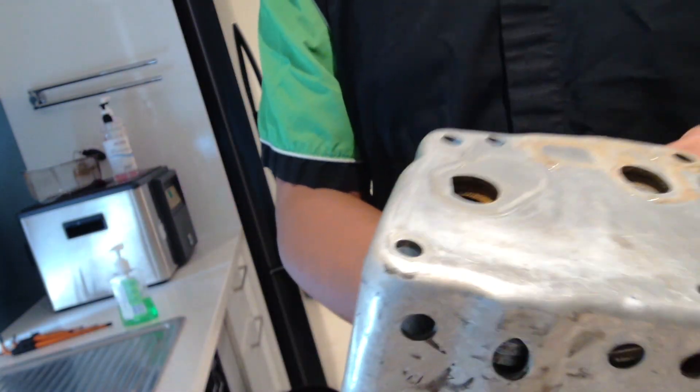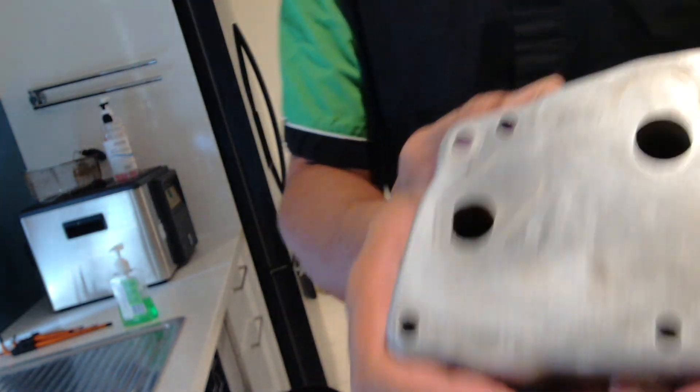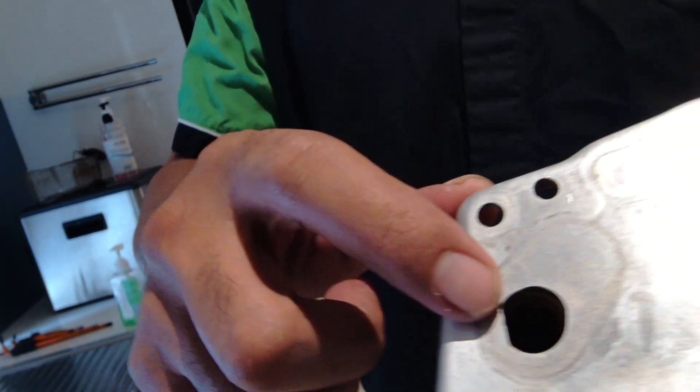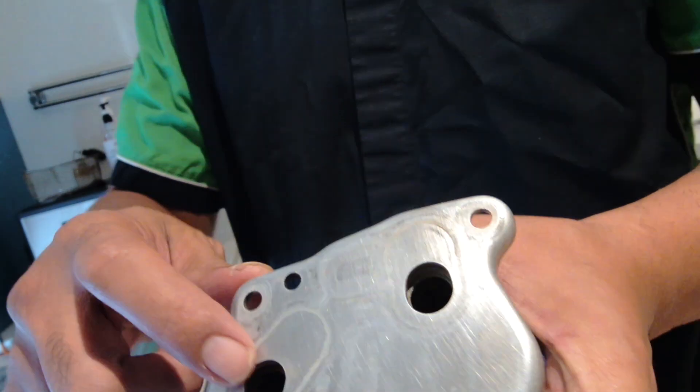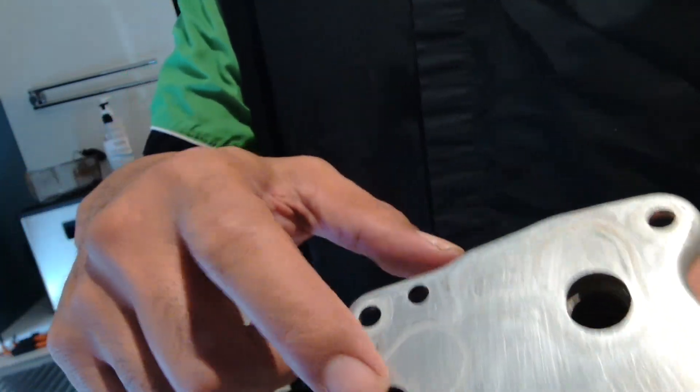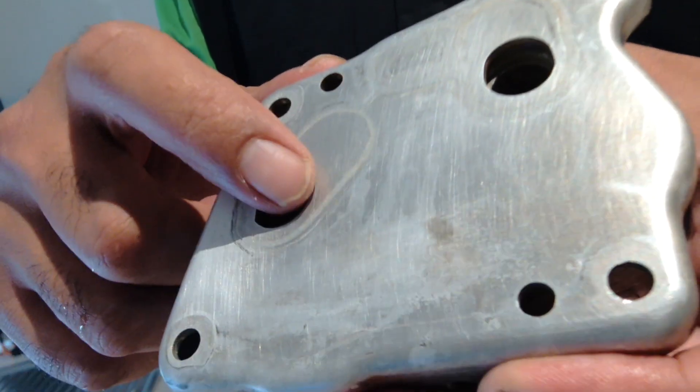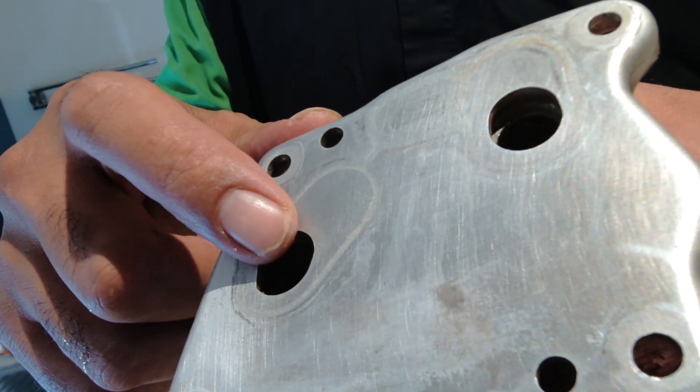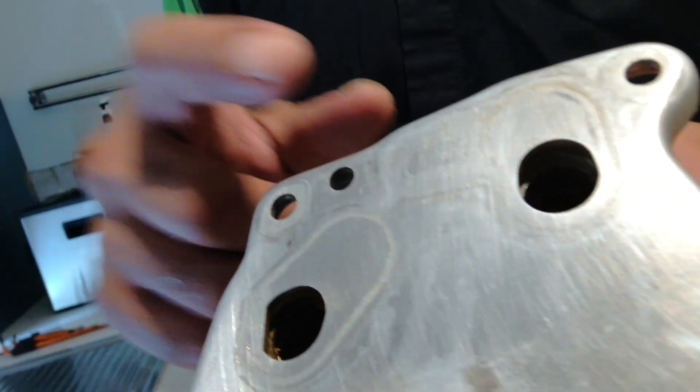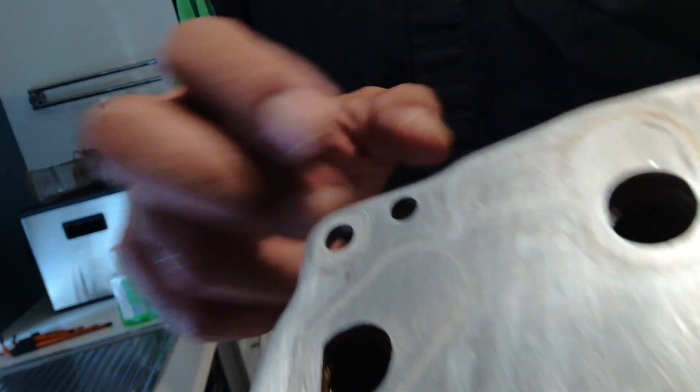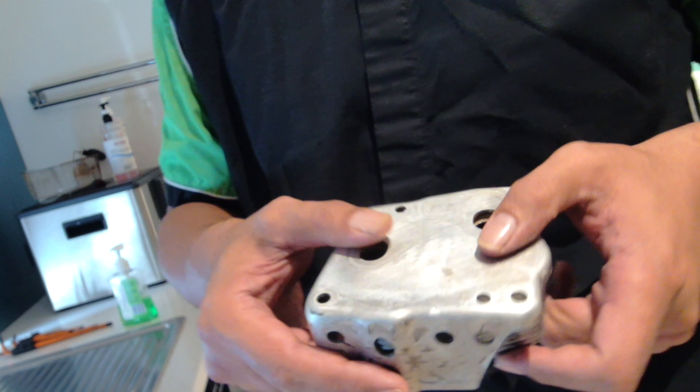If we have a look inside here, this is where your oil will go in into this heat exchanger and then it will come out the other side. If you're able to blow your air into this block on one side and you get bubbles coming out of the plates at all whatsoever, then you know that you've found the problem with these exchanger plates.